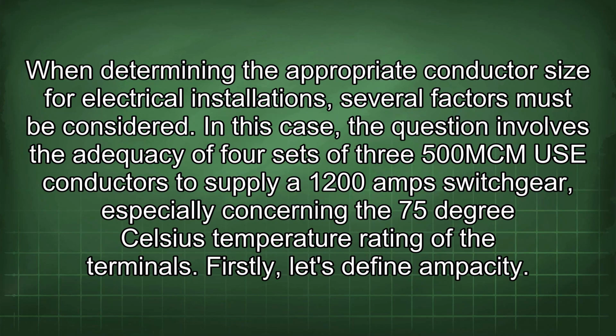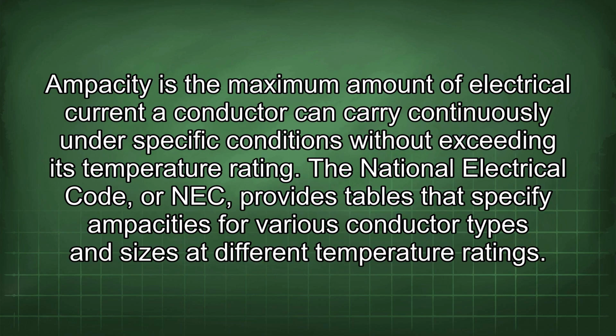When determining the appropriate conductor size for electrical installations, several factors must be considered. In this case, the question involves the adequacy of 4 sets of three 500 mcm conductors to supply a 1200 amps switchgear, especially concerning the 75°C temperature rating of the terminals. Firstly, let's define ampacity. Ampacity is the maximum amount of electrical current a conductor can carry continuously under specific conditions without exceeding its temperature rating.